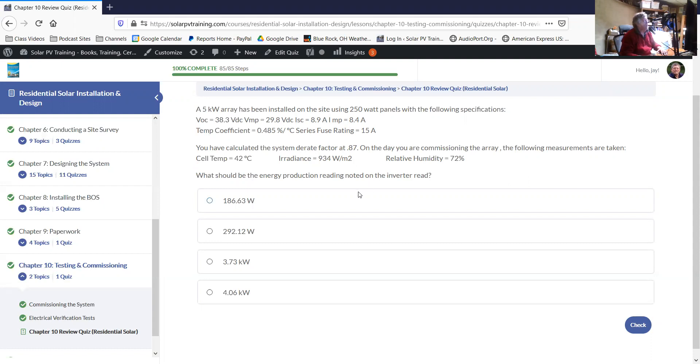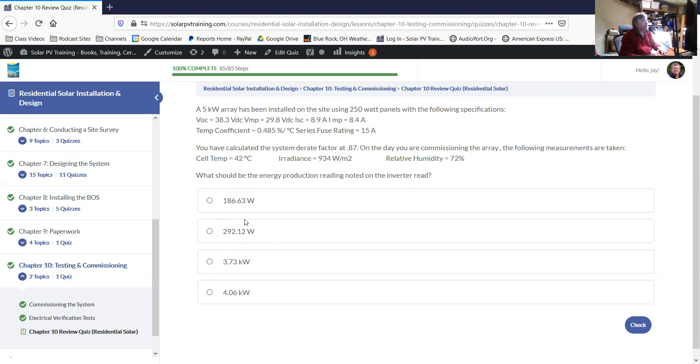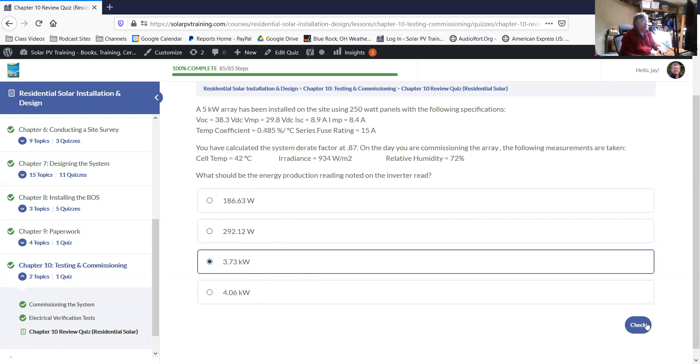We're expecting the system to then have fewer amps than normal. It's telling us the derate factor is 0.87. So that's with all our losses, our system losses. So what you're hoping to do is test at the panel, what's the irradiance, what's the temperature of the cell, not the ambient air temperature. And then you're going to see how much would I expect the system to be producing under these conditions. Looking at this, we would expect it's a 5kW system. So it's going to be less than 5kW. It's either going to be 3.73 kilowatts or 4.06.